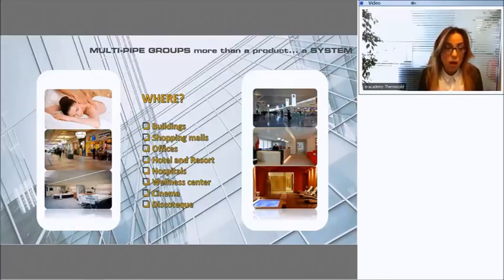Typical applications can be shopping malls, office buildings, hotels and resorts, hospitals, wellness centers, cinemas, discotheques. Why? These are typical applications of a multi-pipe system because this type of application usually requires cold and hot water at the same time. Think about hospitals. You need to produce chilled water for the air conditioning in the surgery room, and you need to produce hot water for the space heating.